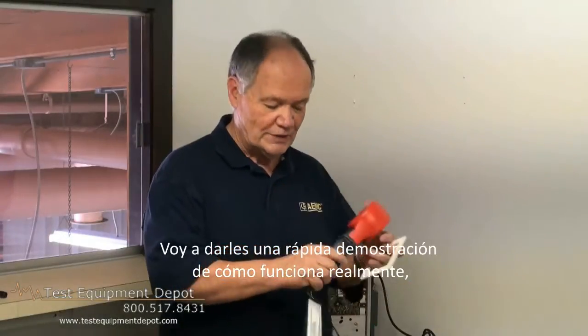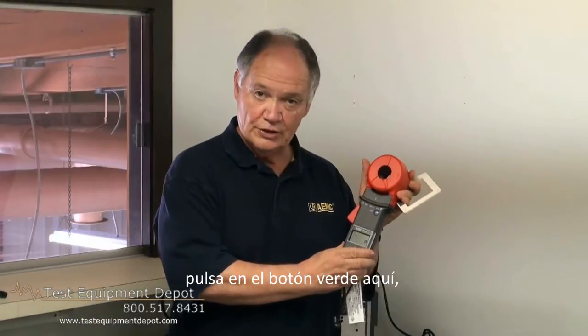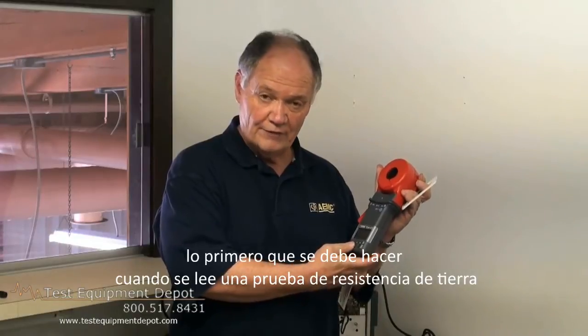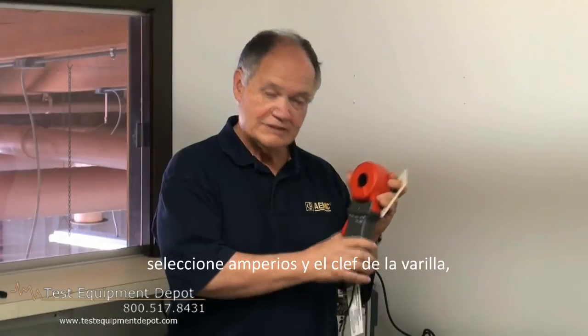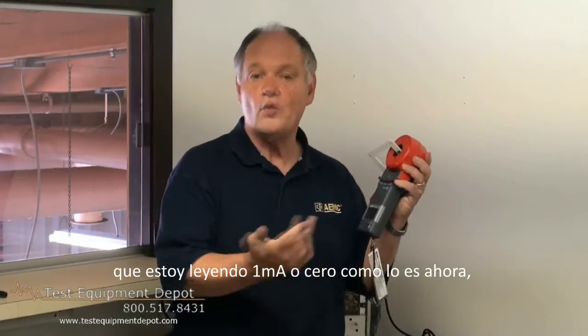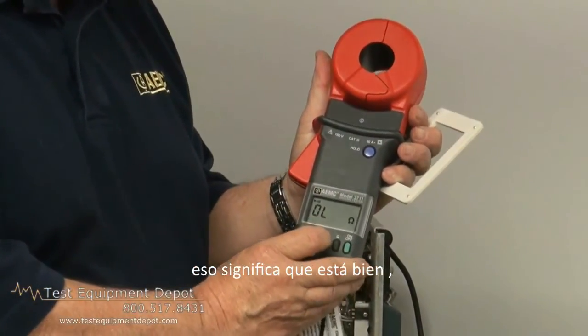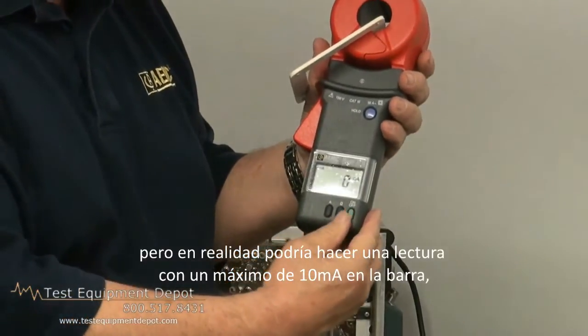I'm going to give you a quick demonstration of how it actually works. We press the green button here and turn it on. First thing you should always do when you read a ground rod — remember, we don't have to disconnect this rod; the rod is still connected. We select amps and clamp it on the rod. I'm reading one milliamp, or zero, as it is right now, so that means it's fine. I don't have any problems. But I could actually make a reading with up to 10 milliamps of current on the rod.